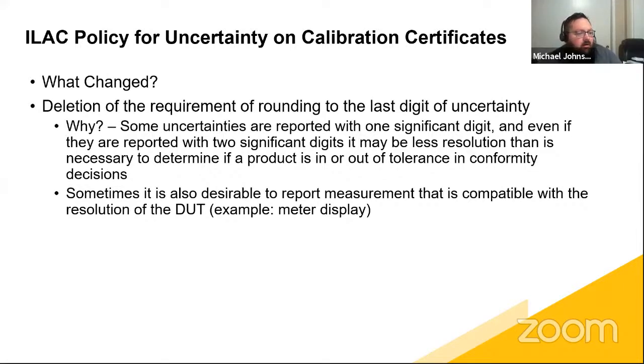So next from Bob, with the changes from BMC to CMC, how should labs that offer measurements of both avenues, meaning those that would fit into BMC like a standard resistor, and those that would fit into CMC like the calibration of an 8508, report the measurement uncertainty when it falls below the CMC? Likely rare, but I could see instances where a lab would have to revert to the SOA reported CMC. For external calibrations, when a lab is not so concerned with TURs further down the line, it's not an issue to default to the CMC. But for labs that calibrate their own standards, the default to CMC could cause TUR issues.